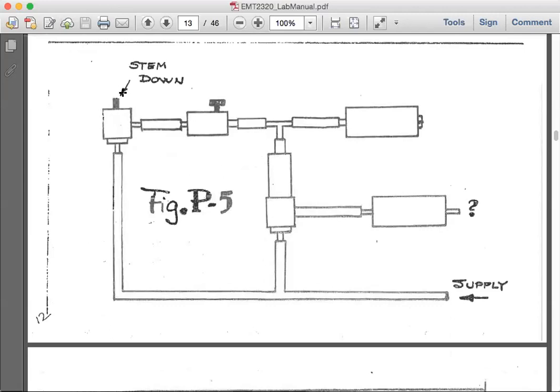And when you press it down, you allow the pressure from the bottom of the three-way valve going into this hose and through the flow control. As we mentioned, the arrow on this flow control is pointing to the left. It means that controlled flow is from the right to the left, and from left to right there is a free flow. So at this stage, this flow control does not control the flow. There is a free flow entering into the system as you press down the stem.